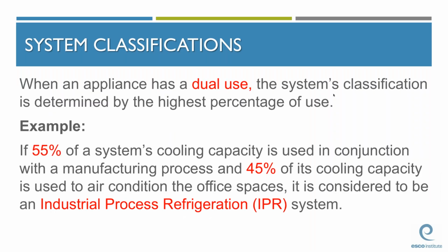Some appliances are used for multiple purposes and will fall into more than one of the three categories that were just outlined. These systems are referred to as dual-use systems. When an appliance has multiple uses, its classification is determined by the highest use percentage. So if 55% of a system's capacity is used to provide process refrigeration for its manufacturing lines, and 45% of its capacity is used to air condition the office spaces, this system would be classified as an industrial process refrigeration system because the IPR aspect of the system is taking up more than 50% of the system's capacity.